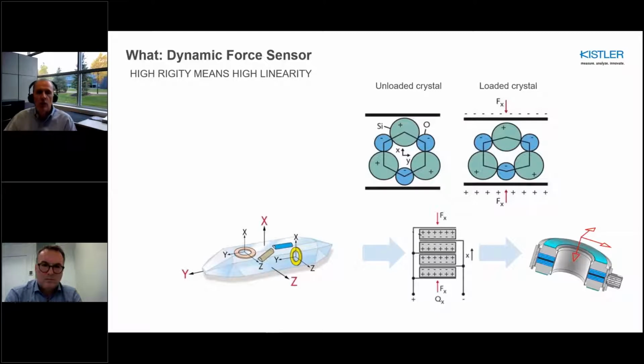Dynamic force sensors utilize piezoelectric crystals. A unique property of piezoelectric crystals is that when they're mechanically loaded with force, as shown in the upper portion of the slide, the created stress causes an atomic level displacement, which in turn generates an electric charge on the upper and lower surfaces of the crystal. This signal output, in picocoulombs, is directly proportional to the applied force.